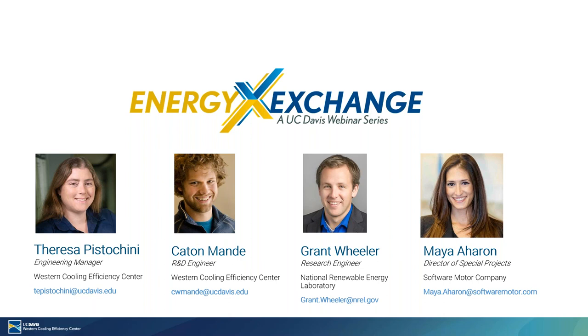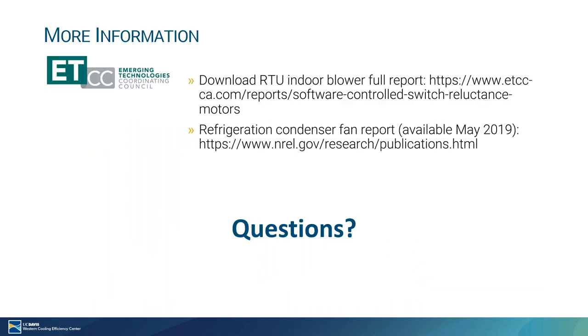Great. Next question, power factor at various speeds and loads. If you go to our detailed report at WCEC, we have power factor data in there for the benchtop dynamometer testing. The end story is that the differences were very small. I think there might have been a statement on one of the slides, but the differences were very small, and in some cases the SMC motor was slightly better, in some cases the induction motor was slightly better, but it's negligible. Grant, did you want to add anything to that? No, we didn't have any analysis on power factors. Okay. There are very detailed plots in that first report that's referenced.